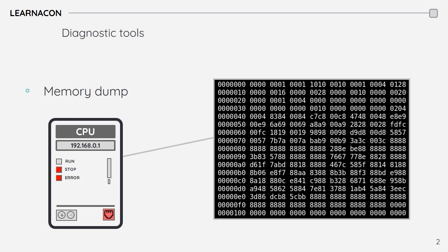Depending on the type of the PLC, technical experts can verify the information from the system dump and find out which code block's execution caused the PLC to stop working, what the values passed to the block were, and even which line of the program triggered the crash. It may happen that the code is fine, but the passed value has not been validated. For example, a division by 0 or an out-of-range array index.